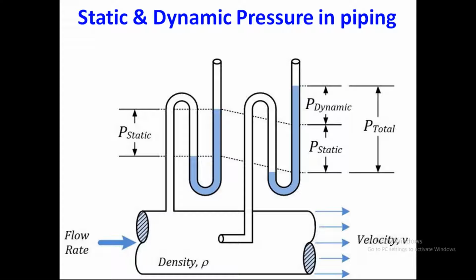That is one aspect. If you measure the static pressure, it is measured just on the periphery of the pipe. If the same probe is inserted into the center of the system, sometimes technically called an Annubar, it can measure both static and dynamic pressure. The dynamic shows the velocity aspects, so pressure dynamic plus pressure static is the total pressure. Any fan is defined by the total pressure. For convenience, the OEMs and industries give the total fan efficiency and the fan static efficiency. Whichever is measurable and monitorable by the industry, you measure it and check the efficiency of your fan.